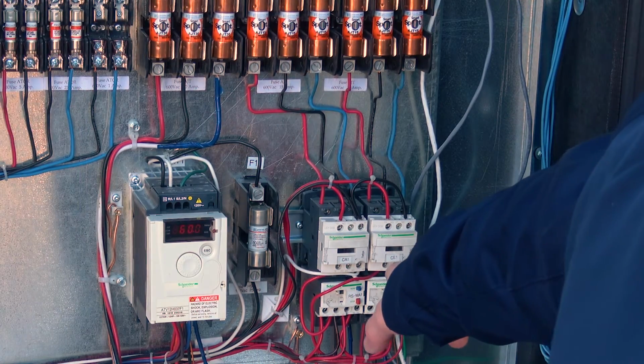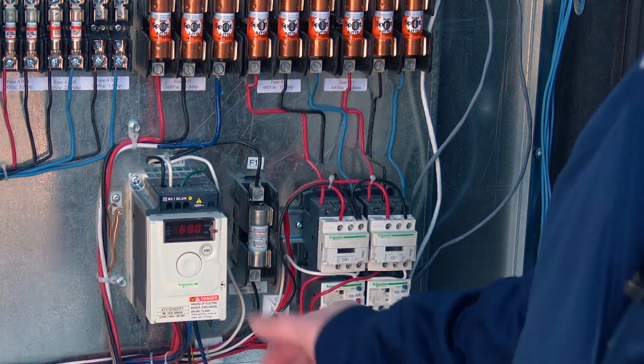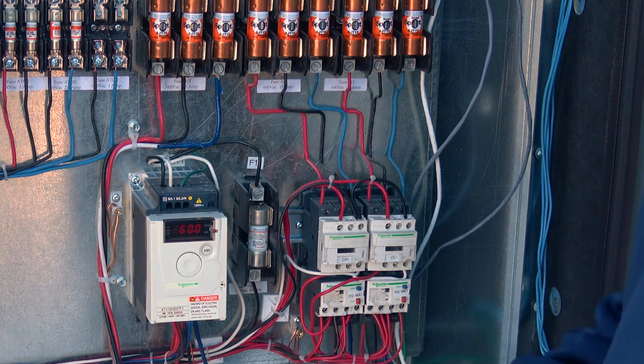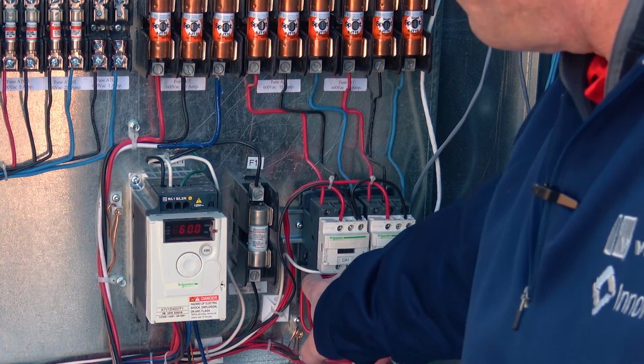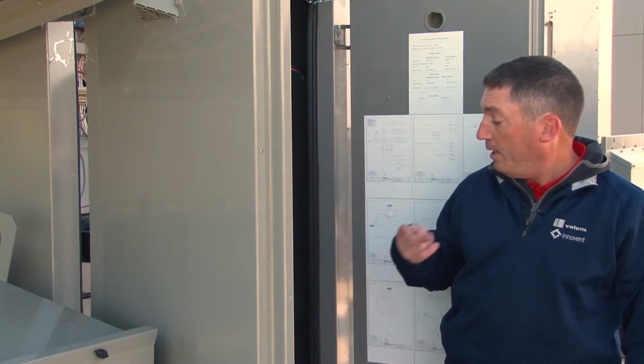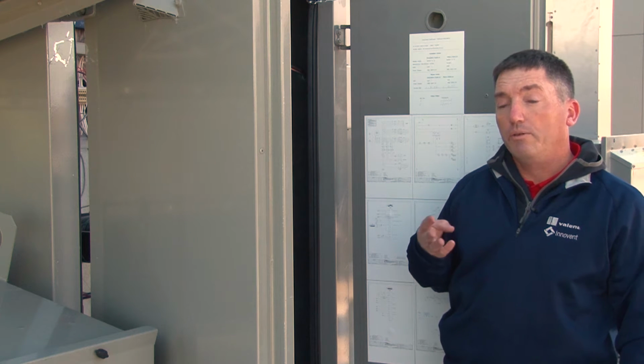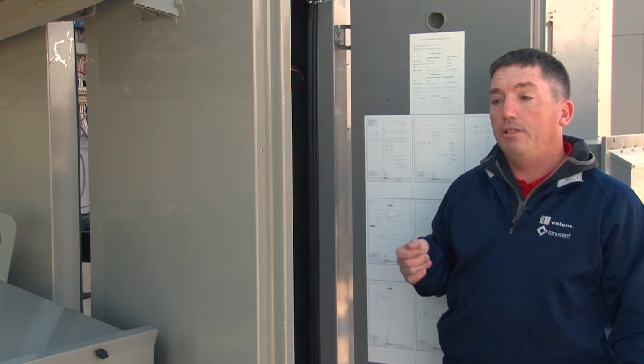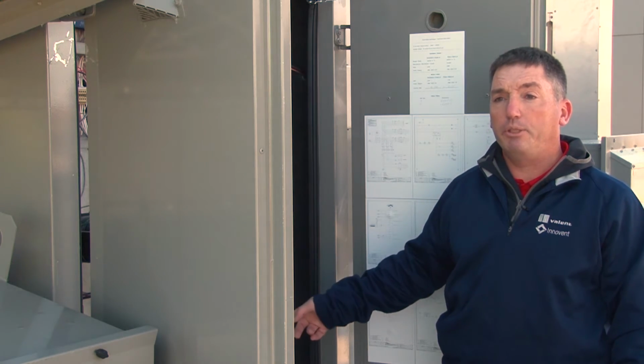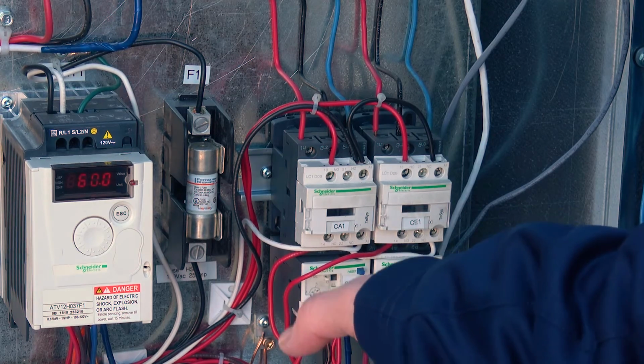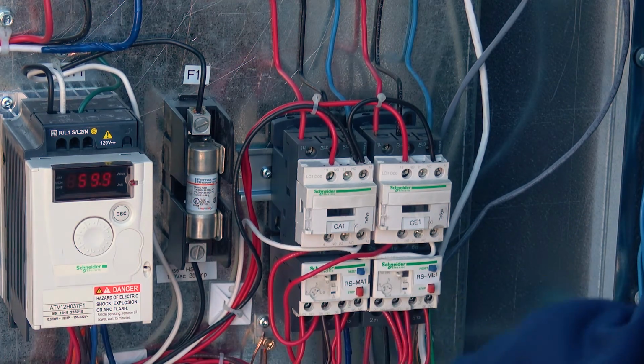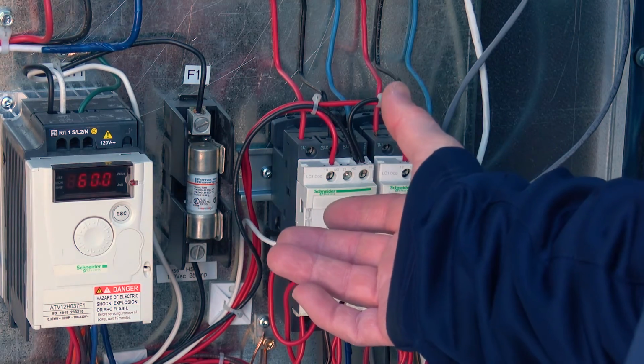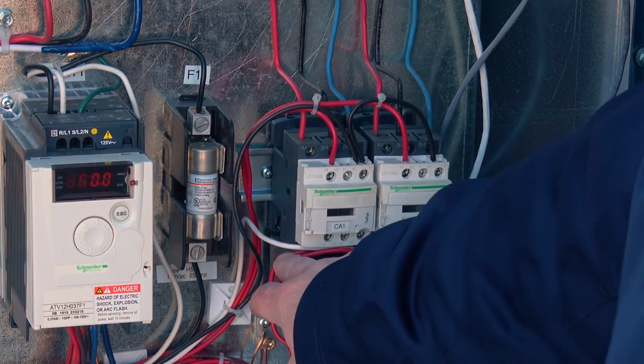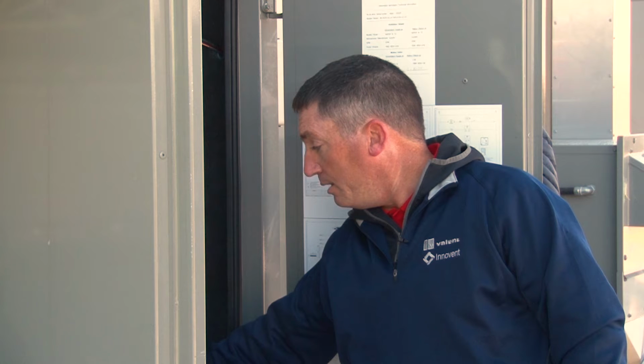Down beside the drive, we have 2 contactors. One is for the supply blower and one is for the exhaust blower. At the bottom of the contactor, we have what are called overloads, and there's 2 buttons on the overloads. One is blue and one is red. If the motor has exceeded the amperage, this acts like a circuit breaker, and it will actually shut the motor down. So if you come up and you notice that one of the motors isn't running, the first thing to check would be the overload. There's a small box that has a little flag. If it's tripped, there's going to be a white line, and the easiest way to test it is just to press the reset button.